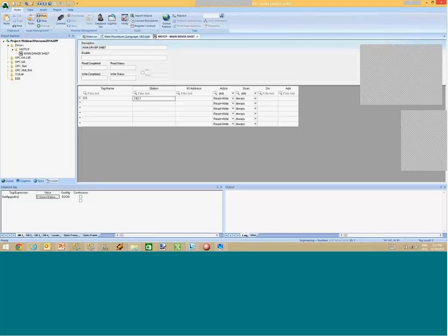I do not have a Modbus interface in my computer, but it would be the IP address, colon, the TCP port, colon, the Modbus ID of the PLC, the I/O address. So I'm not sure what address it is, but let's say it's 4x1, holding register 1. And if you want to write only, if you never want to read, or if you cannot read this value for whatever reason, you can use here write.